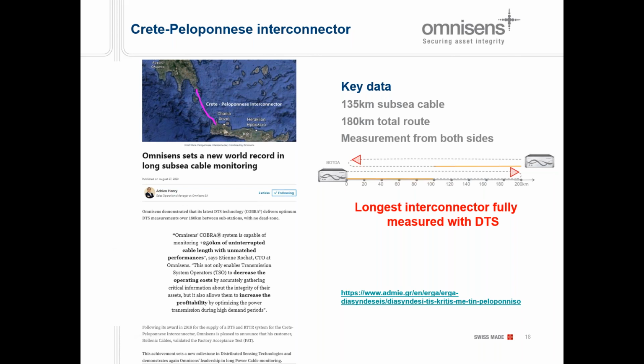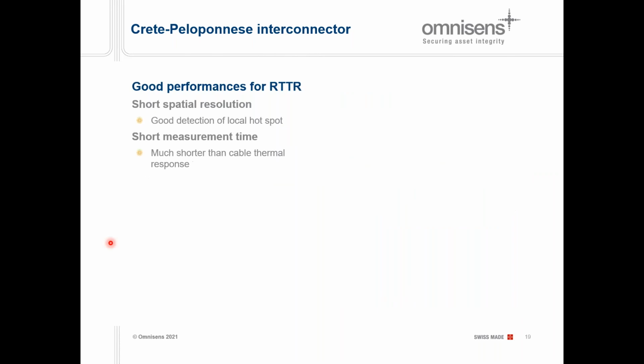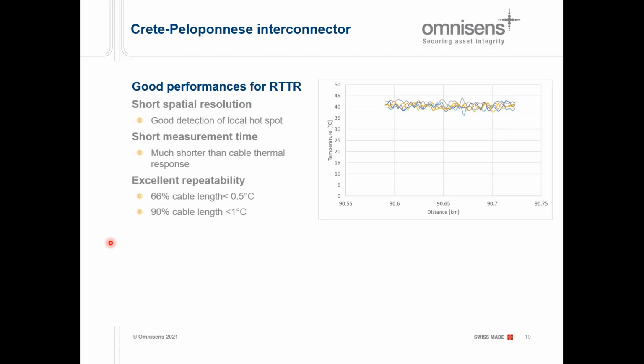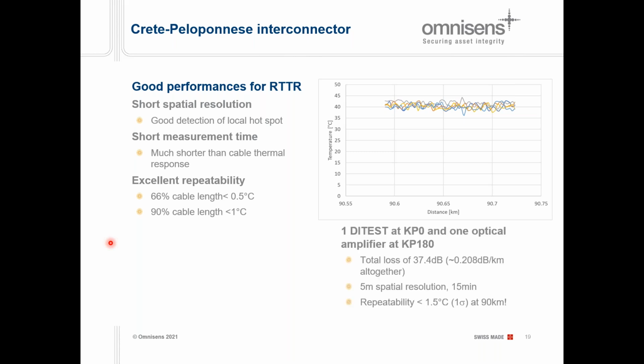In that Crete-Peloponnese interconnector, we tried to maintain short spatial resolution all the way to detect hotspots. We tried to maintain short measurement times, so we really pushed the performance. At the end of the day, two thirds of the cable were measured with a repeatability of less than 0.5 degree, meaning that if you do the measurement again and again, you always get the same value. It's only when you get to the middle of the cable that you start having slightly wider repeatability. Eventually, when we made the test shown in the figure, we had a total loop loss of about 37.4 dB one way, which is slightly above 0.2 dB per kilometer, with 5 meter spatial resolution and 15 minutes measurement time.